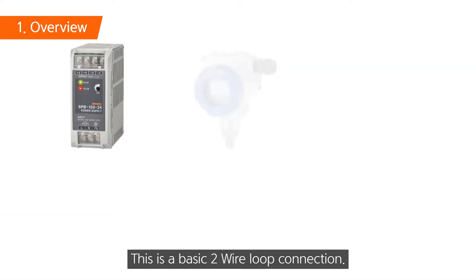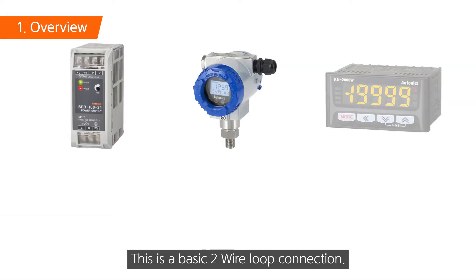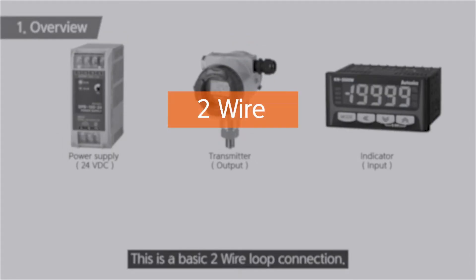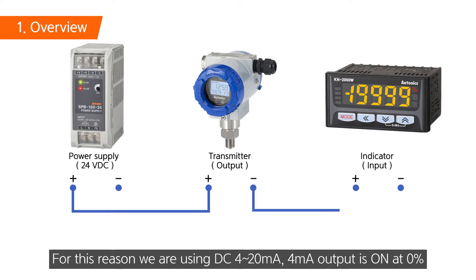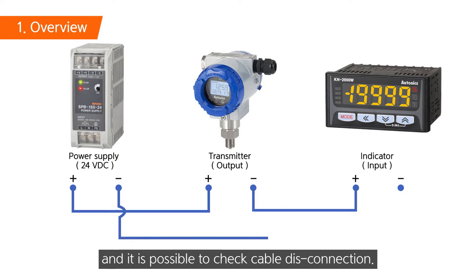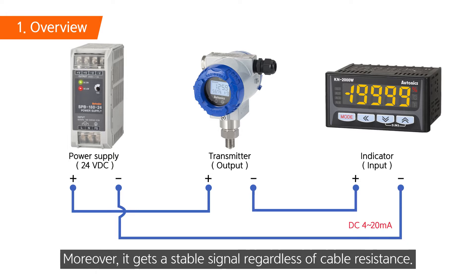This is a basic two-wire loop connection. For this reason we are using DC 4 to 20 milliampere. 4 milliampere output is on at 0%, and it is possible to check cable disconnection. Moreover, it gets a stable signal regardless of cable resistance.